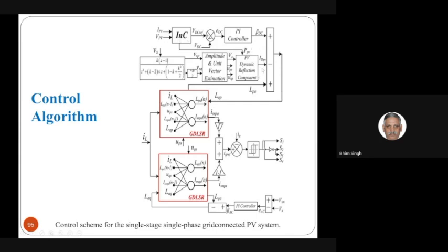So with this, we are able to have another component of the grid current, which is a kind of disturbance in the system. So we take a feed forward, and this enhances the response of the system as well as reduces the burden on the PI controller, because this is a reference grid current. The reference grid current now knows in advance that power is coming up. So certainly the PI control need not do so much exertion.